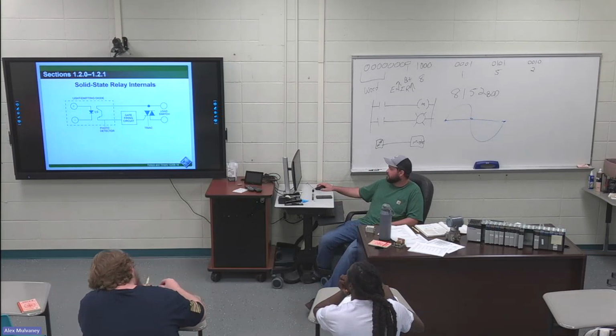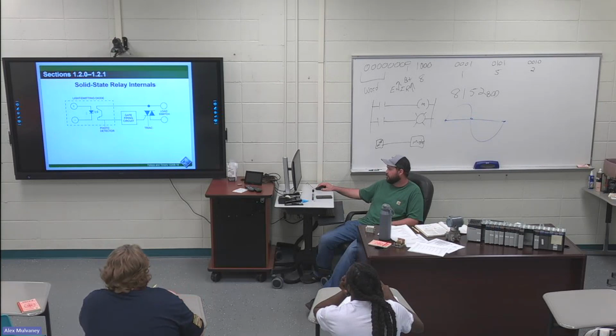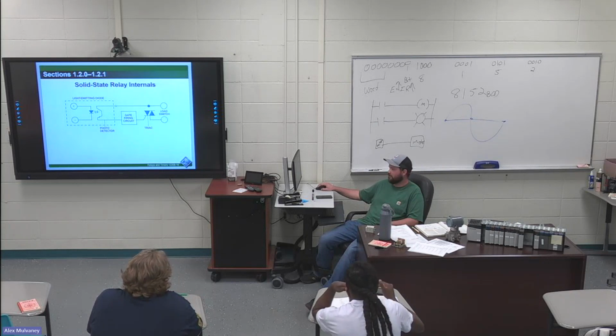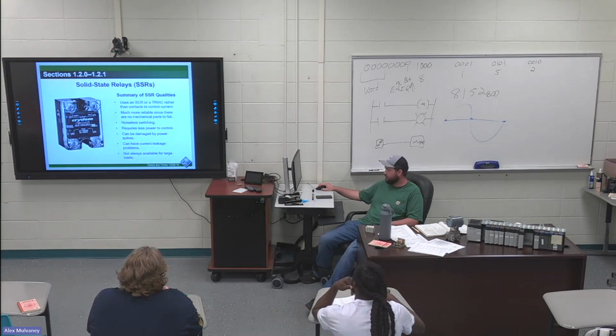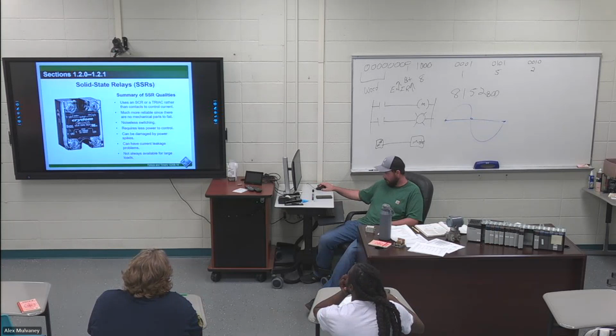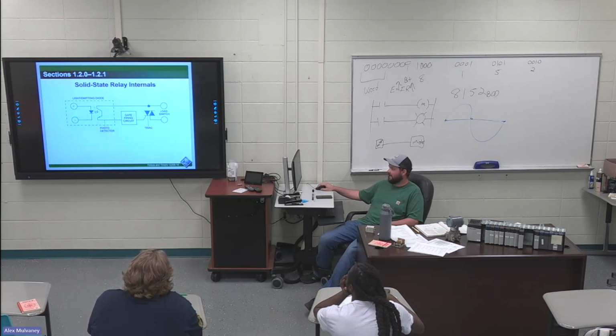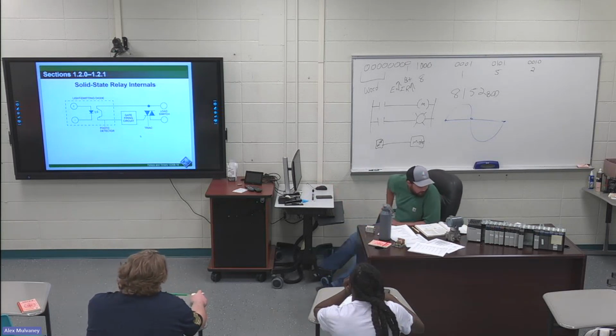So for a solid state relay, you have your power coming in on this side. Anybody know what this is the symbol for? It's a diode. More specifically, it's an LED, light emitting diode. So whenever power flows through, it actually turns on a light, and then you have a photodetector on this side. And that's what works with a triac to turn this switch on or off. So in the solid state relay, you'll actually have a light inside of here. Actually, I think it's right there. That will come on, and that's an actual part. No moving parts, but there's a visual part to these that work. But definitely good for machines that vibrate and stuff like that.